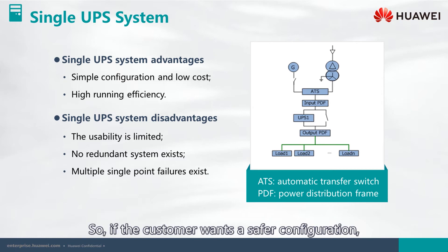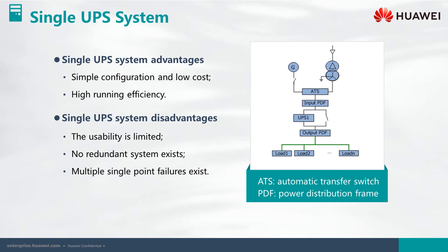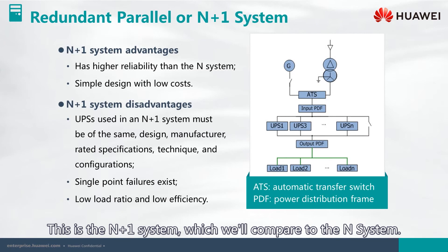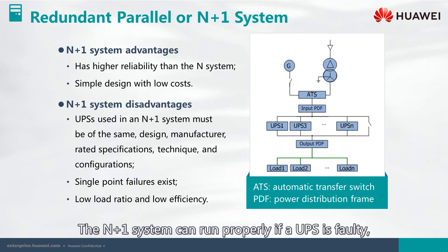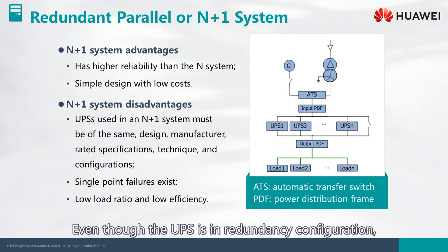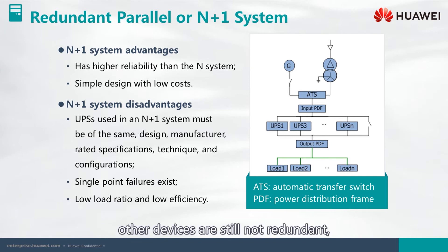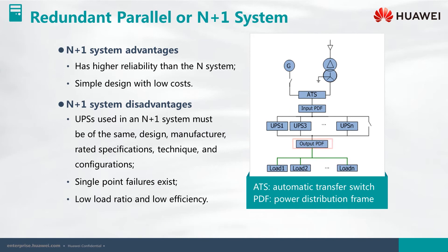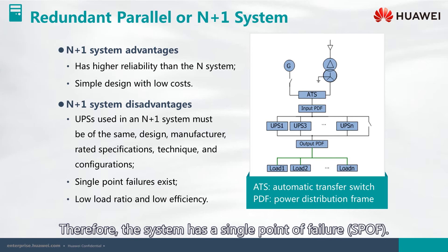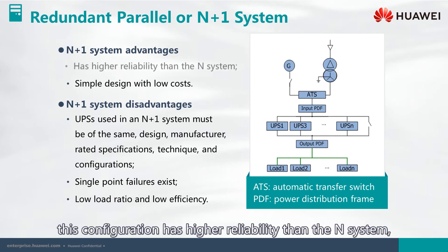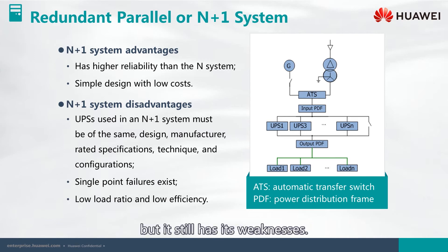If the customer wants a safer configuration, we can recommend the N plus one system. The N plus one system can run properly if a UPS is faulty, so it's more reliable than the N system. Even though the UPS is in redundancy configuration, other devices are still not redundant, such as the ATS, input power distribution frame, and output power distribution frame. Therefore, the system has a single point of failure, SPOF. This configuration has higher reliability than the N system, but it still has its weaknesses.